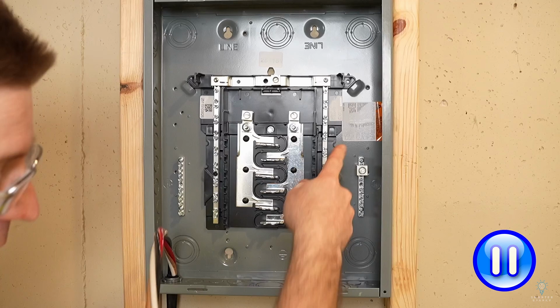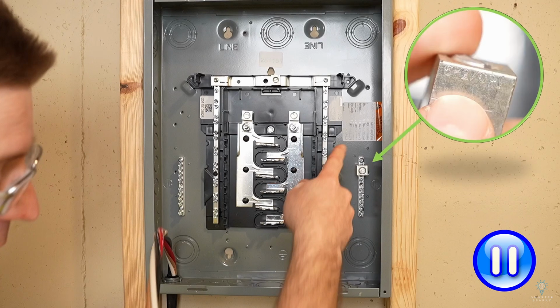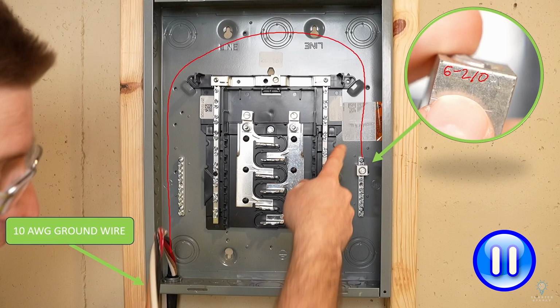Hey, Dustin from the future here. I just want to clarify something here. Remember earlier we saw that that lug was rated from 6 gauge through 2/0 gauge? Well, I've actually got a 10 gauge ground wire in my 6-3 cable here. So that 10 gauge ground wire cannot come up and over and land in that lug. That lug is too big for that wire. So instead what we're going to do is just come out of this cable here, and I'm going to land it right here on this closest ground bar.